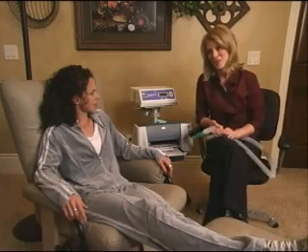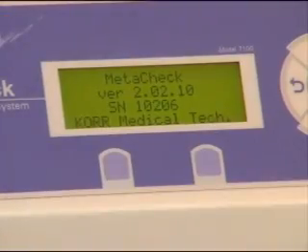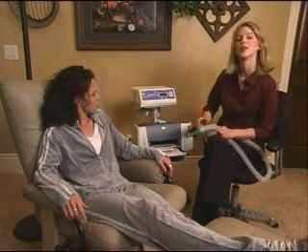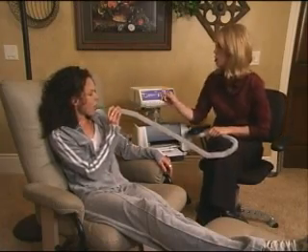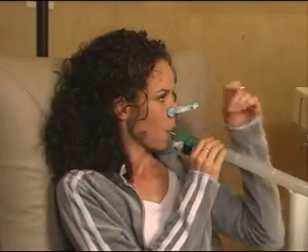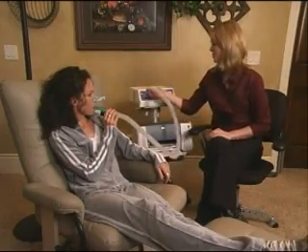We're now going to show you what happens during actual testing. Elizabeth here will be our client. Simply turn on the device and wait while it calibrates — this usually takes two to three minutes. Once the display reads calibration complete, we're ready to hand the mouthpiece to Elizabeth. You'll want to seal your lips around the mouthpiece and use this nose clip so that all the air you breathe out will be analyzed by the MetaCheck. Once she's comfortable, just connect the hose to the box.